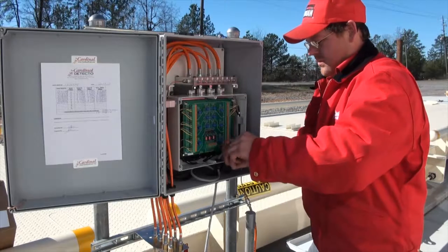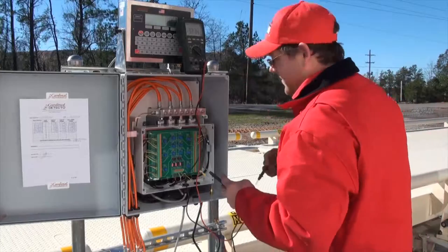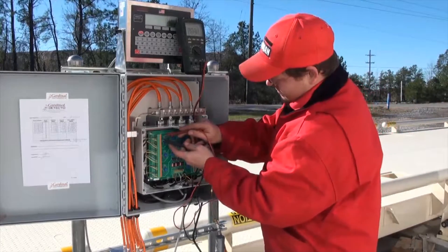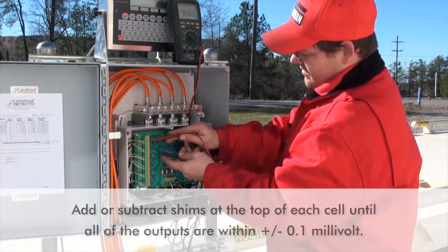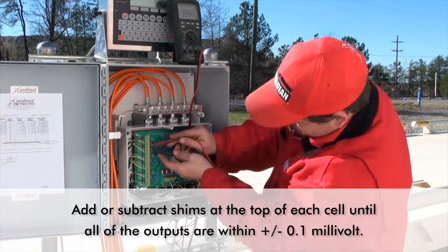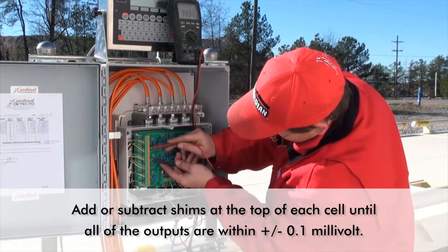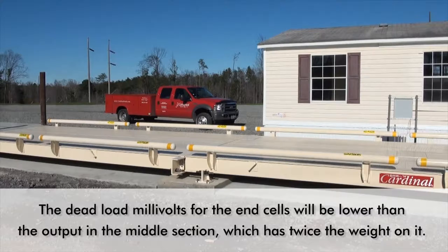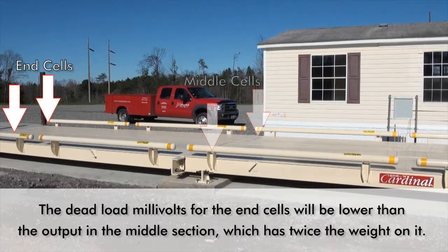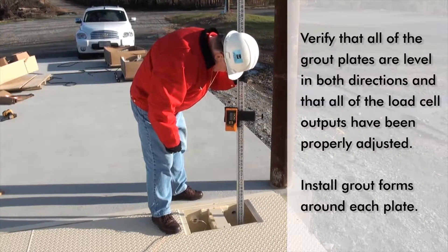Attach the weight indicator to the totalizer junction box using shielded cable and following the directions in the weight indicator owner's manual. With the indicator power on, measure the millivolt output from each load cell to make sure that the load is evenly distributed among the load cells. Add or subtract shims at the top of each cell until all of the outputs are within plus or minus 0.1 millivolt. Test data for each of the load cells is located on the inner door panel of the totalizer. Please note, the dead load millivolt output for the end cells will be lower than the output for the cells in the middle section since they have twice the amount of dead load on them. Verify that all of the grout plates are level in both directions and that all of the load cell outputs have been properly adjusted.